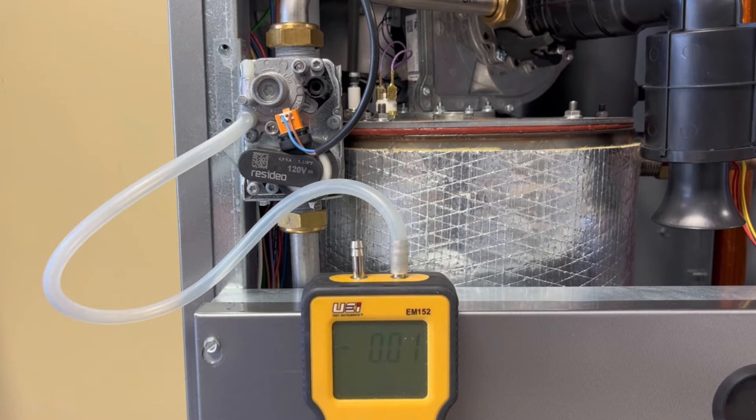Now you want to adjust the low fire adjustment screw while the boiler is running in low fire until the pressure on the manometer reads zero.